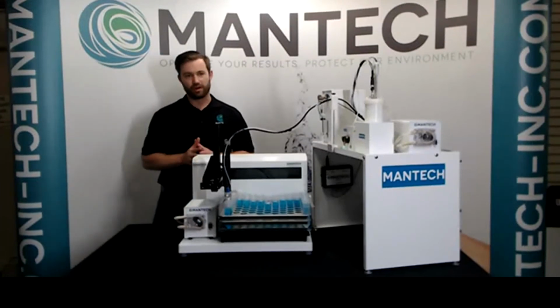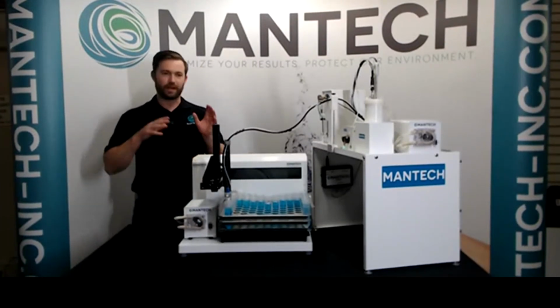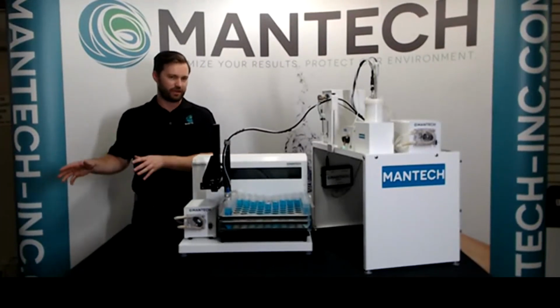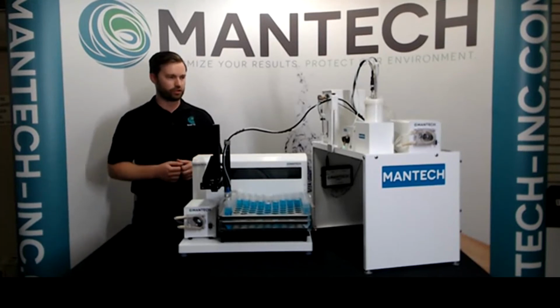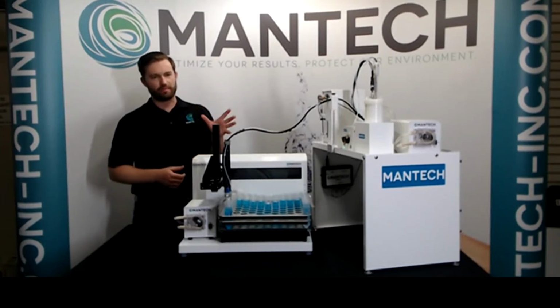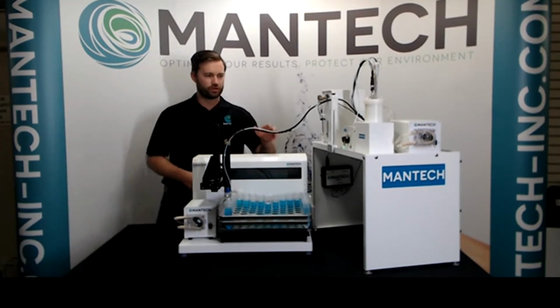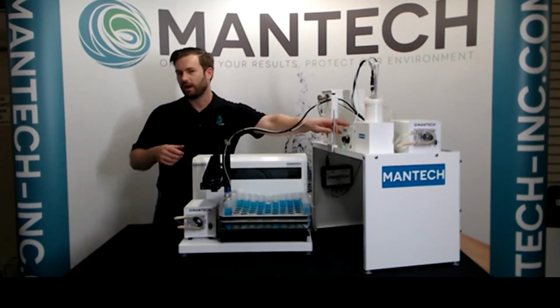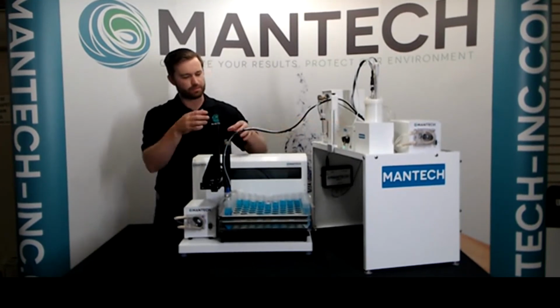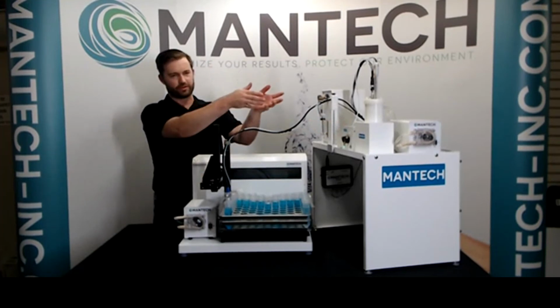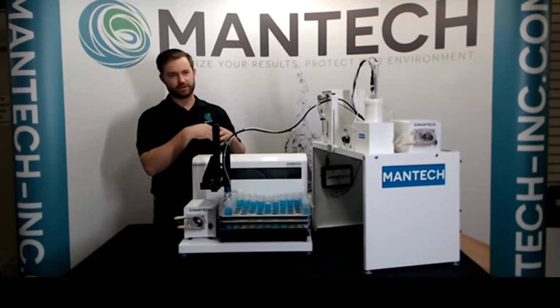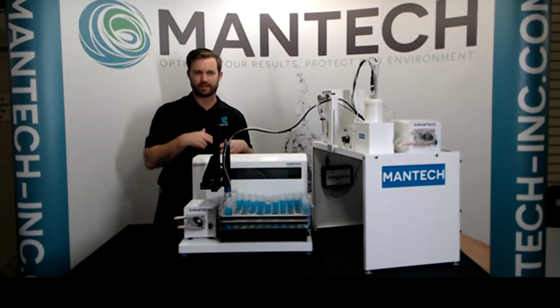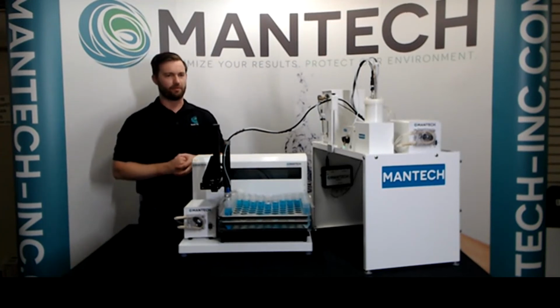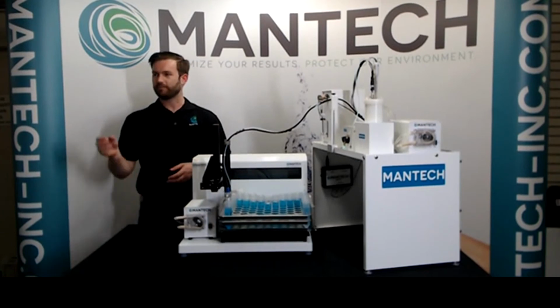The MT100, one of the biggest benefits of this compared to the other models, the MT30 and the MT10, where you're measuring the tube, is this one has automated pipetting. So it features an automated pipetting pump right there, and that's drawing the sample up from the auto sampler, primes the line first, and then dispenses an accurate 10 ml of that sample for the alkalinity titration. So that's what's going on right now.